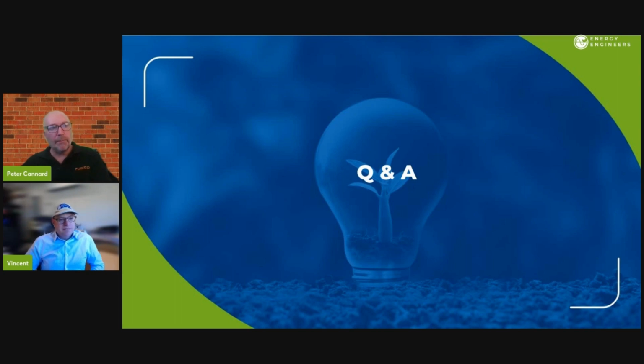That's right, and it can actually result in far more serious consequences as well. We got an inquiry the other day for an active harmonic filter, because the retailer or distributor had written to one of their customers that have 3-4 large pumping applications, saying that the harmonic content measured by them is too high. They need to rectify this within the next 12-month period, reducing the harmonic content down to, in this case, the Victorian Electrical Code of Practice regulations, or they'll be disconnected. So that's as simple as that.